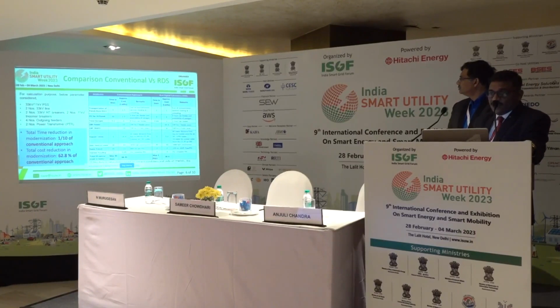So the comparison we have done is with respect to the conventional approach versus RDS, rural digital substation. The time reduction we have envisaged is 1/10th of the conventional approach. If we go with the conventional approach there is so much work to do, even the transportation of CRP panels is a big task. So all these tasks we have reduced, and we found that the commissioning time and modernization time is only 1/10th of the conventional PSS approach, and the cost reduction is around 62.8%.